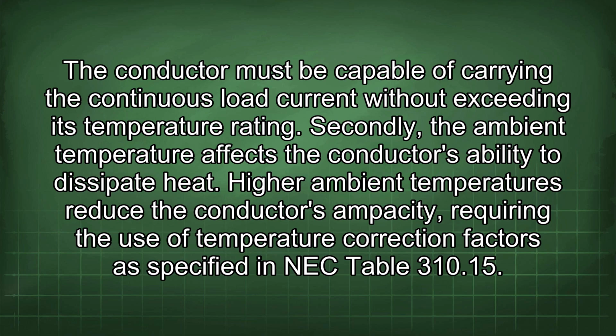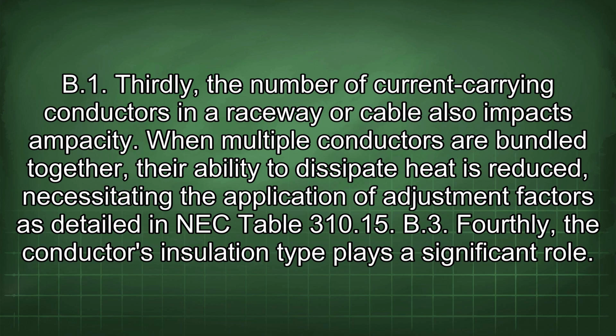Secondly, the ambient temperature affects the conductor's ability to dissipate heat. Higher ambient temperatures reduce the conductor's ampacity, requiring the use of temperature correction factors as specified in NEC Table 310.15(B)(2)(a). Thirdly, the number of current carrying conductors in a raceway or cable also impacts ampacity. When multiple conductors are bundled together, their ability to dissipate heat is reduced, necessitating the application of adjustment factors as detailed in NEC Table 310.15(B)(3)(a). Fourthly, the conductor's insulation type plays a significant role.